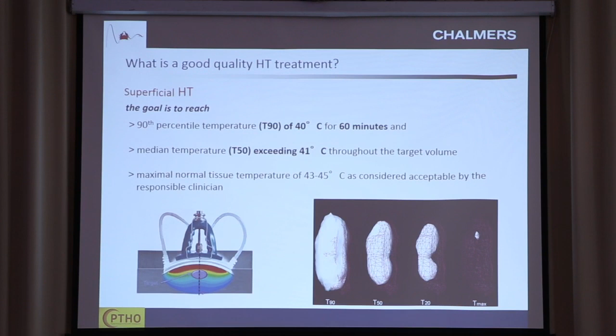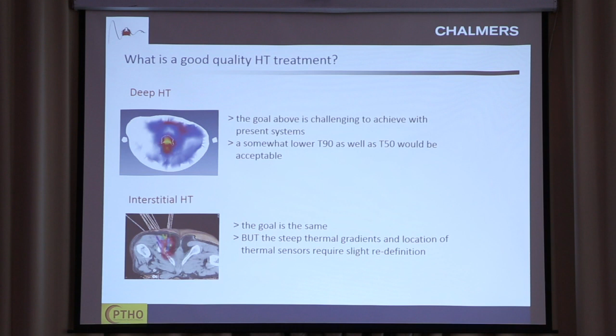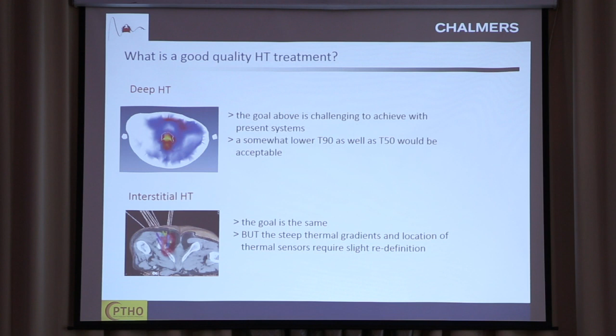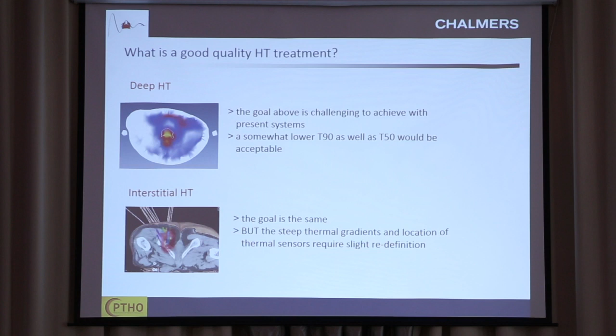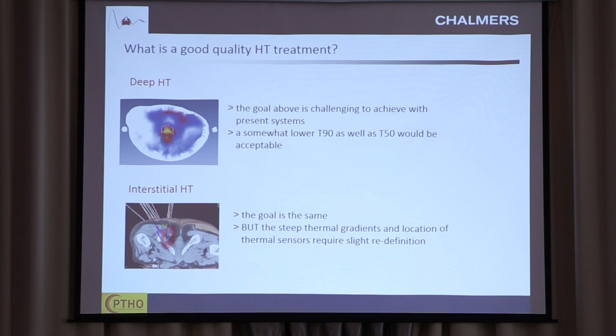So the T90, 90% of tumor, must be covered with temperature at least 40 degrees C for 60 minutes. And median temperature T50 should exceed 41 degrees C through the target volume. And the maximum normal tissue temperature should be between 43 and 45 degrees C. For deep hyperthermia, the goal above is quite challenging with the present systems, so we can accept somewhat lower T90 as well as T50. For interstitial hyperthermia, the goal is the same, but we must be aware of very steep thermal gradients and location of thermal sensors, because I will come to this later in a more specific part of this talk.